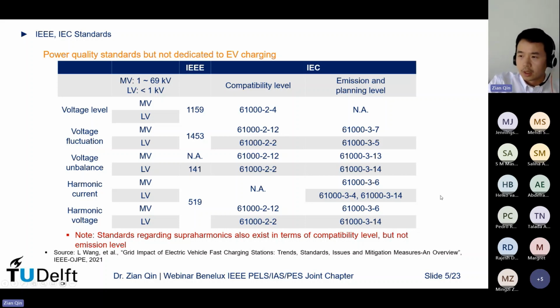Because flickers, harmonics, and also interharmonics have been a problem for a long time, the standardization is kind of mature. There are already mature standards on those kinds of power quality issues. They are not specific or dedicated to EV charging, but for EV charging we can still refer to those standards. However, the standardization regarding supraharmonics is still ongoing. It's because supraharmonics is a relatively new phenomenon that just recently started to get people's attention. So far there is only a compatibility level, but the emission level is not there yet.